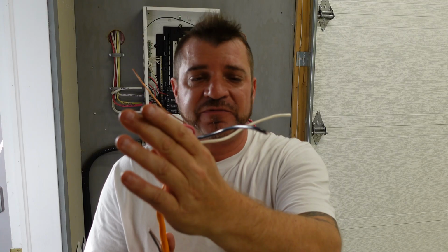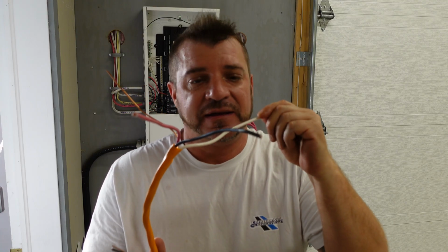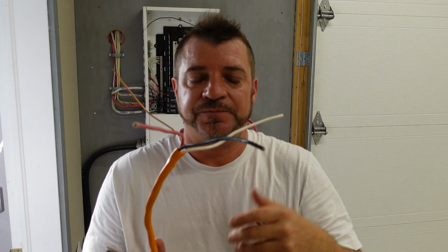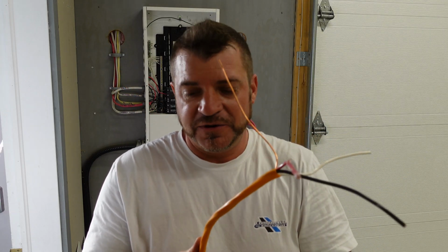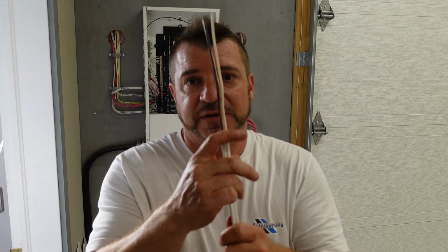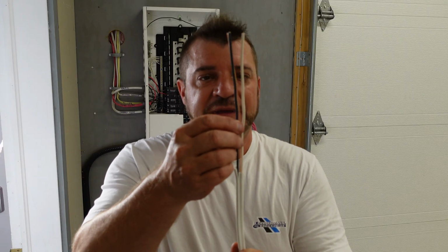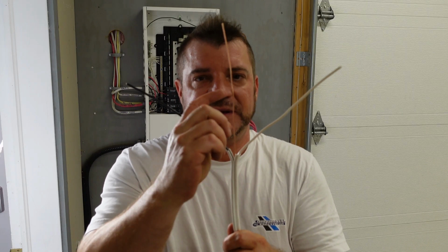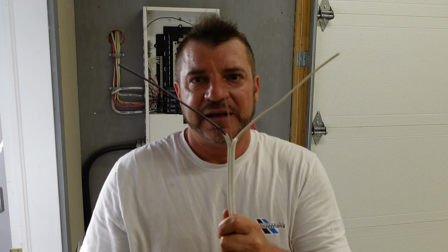So for example, if we have 20 amps on the black and we have 10 amps on the red, then it's going to carry back 10 amps on the neutral, the difference between the two to equal it out. Now, unfortunately, that only applies for 3 wires. 2 wires, which is your standard house wiring, has a black and a white and a ground, okay?